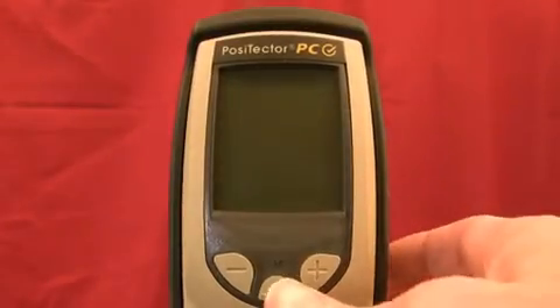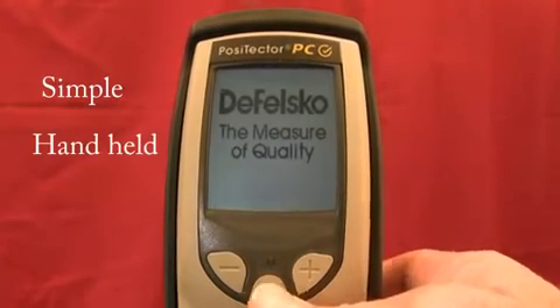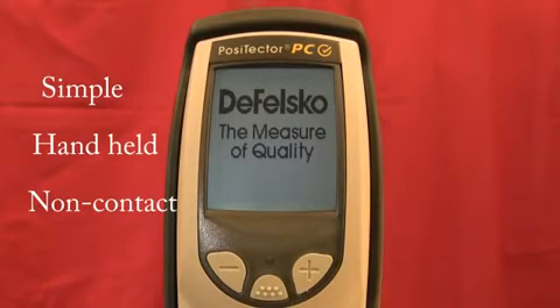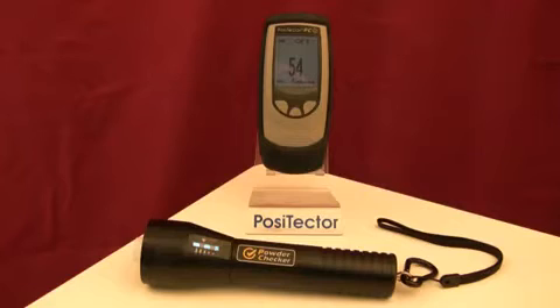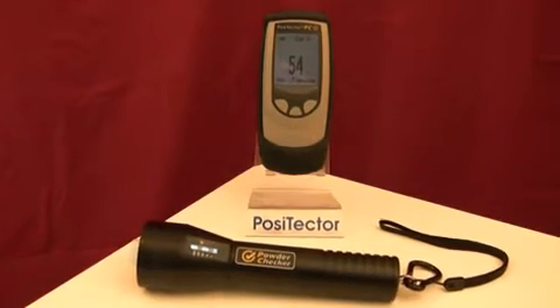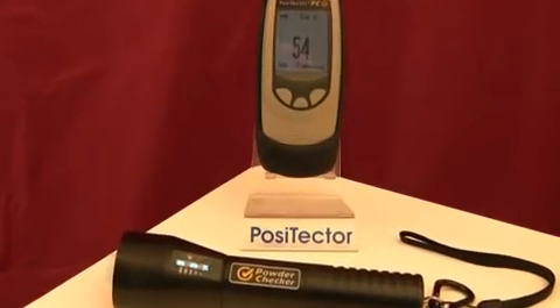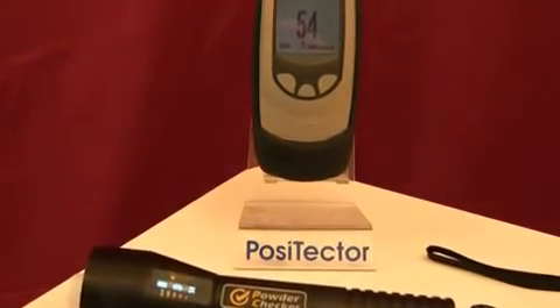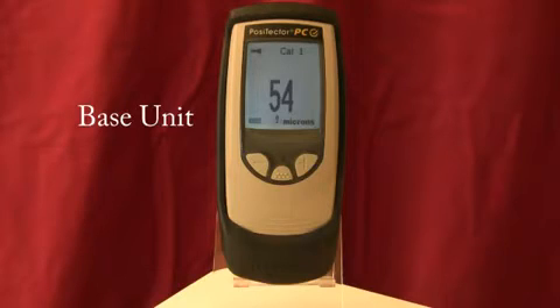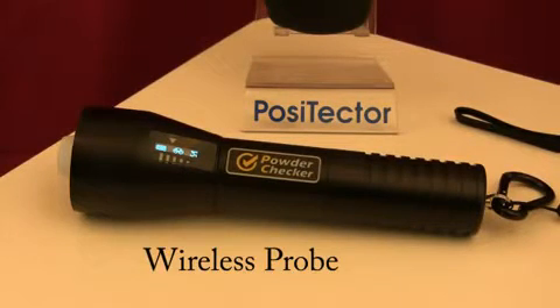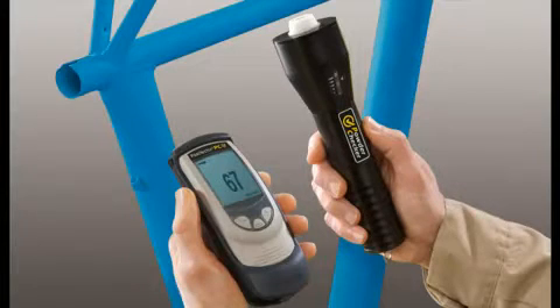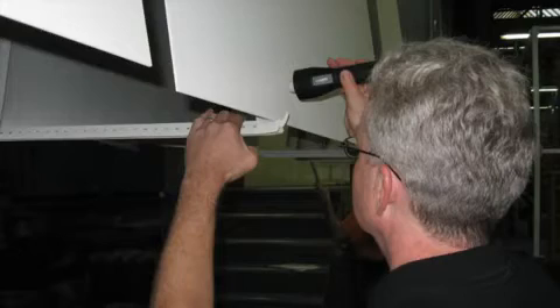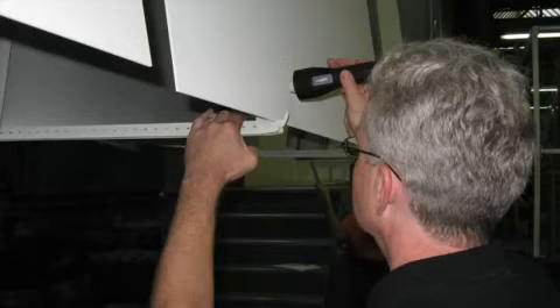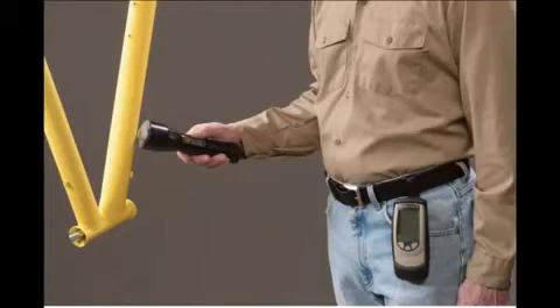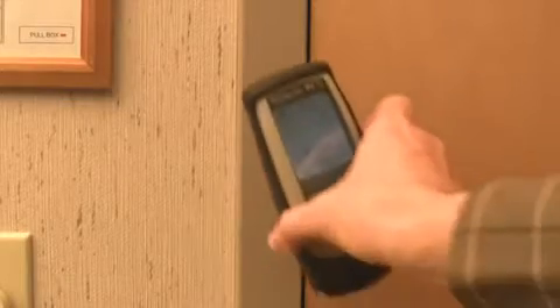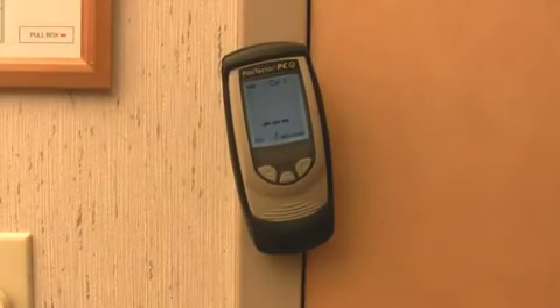The Positector PC powder checker is a simple, handheld, non-contact instrument that measures uncured powder coatings. It uses ultrasonic technology to automatically calculate and display a predicted cured thickness. The instrument consists of a base unit and a probe that communicate with each other via Bluetooth wireless technology. The wireless probe has a range of 10 meters or 30 feet. The base unit can attach to a belt, remain in the carry case, or be conveniently attached magnetically to a nearby steel structure.